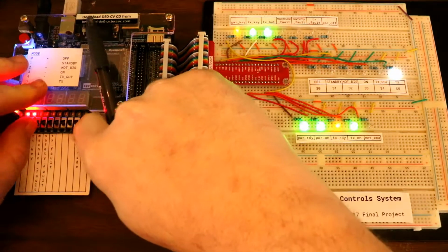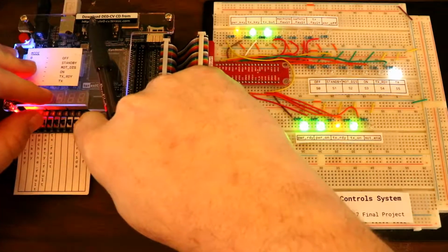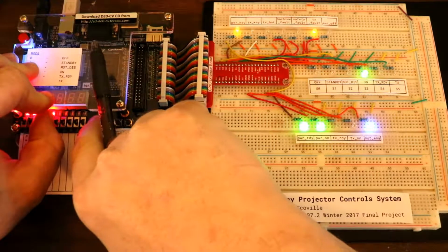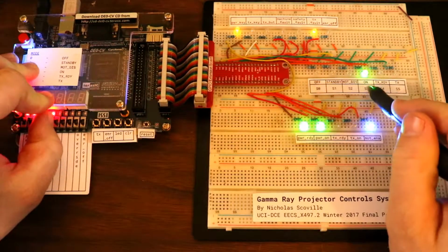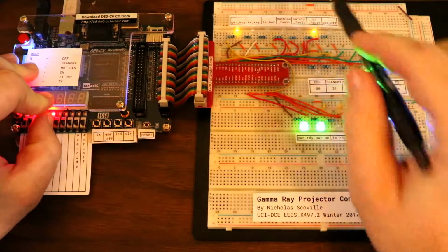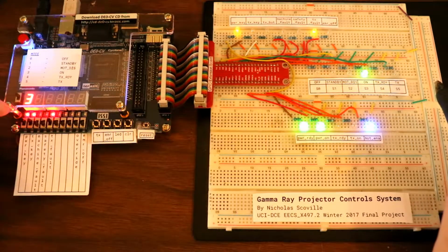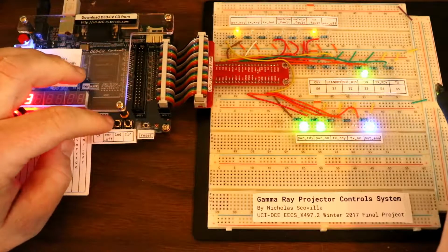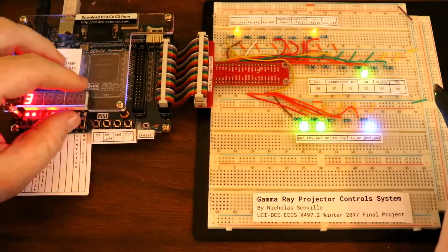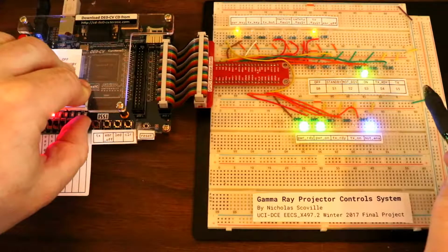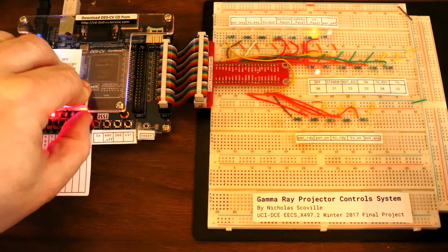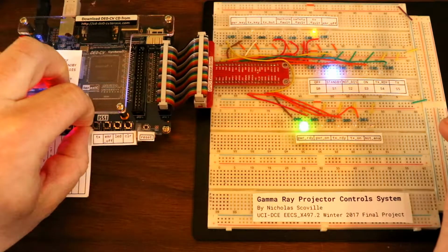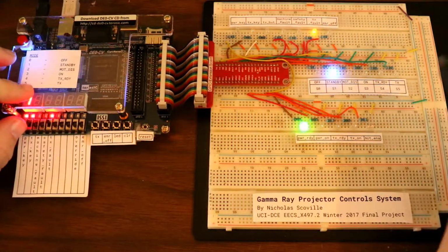If I were to now get a transmit fault while transmitting, you can see that we now drop back to the on state with our transmit fault. From any state, if we get an emergency off signal, it will immediately drop to the off state. When the emergency off signal is cleared, you go back to the standby state.